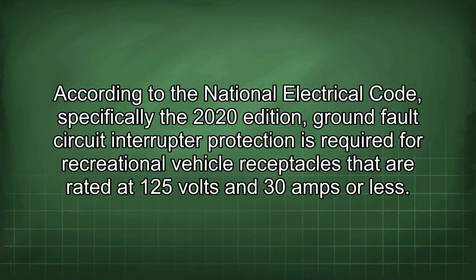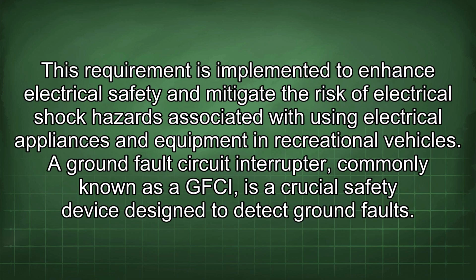According to the National Electrical Code, specifically the 2020 edition, ground fault circuit interrupter protection is required for recreational vehicle receptacles that are rated at 125 volts and 30 amps or less. This requirement is implemented to enhance electrical safety and mitigate the risk of electrical shock hazards associated with using electrical appliances and equipment in recreational vehicles.